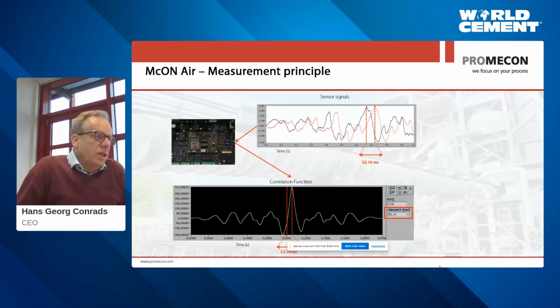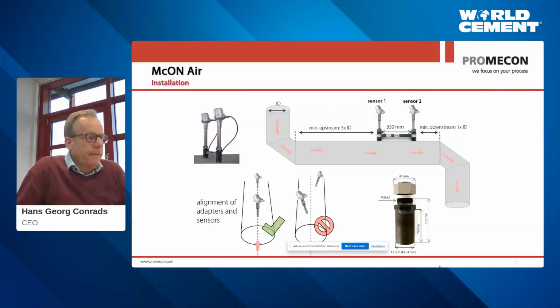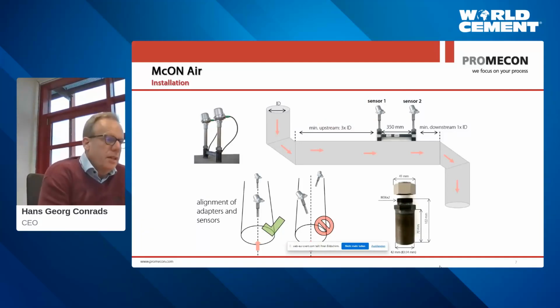What you can do then, of course, is you can compensate the measured velocity by the temperature of the gas and the barometric pressure. And of course, you should also take into consideration the cross-sectional area of the duct that this whole thing is happening in. So you have cross-sectional area times velocity gives you actual flow. And then compensation by barometric pressure and temperature gives you STP flow, standardized temperature and pressure flow. That's it. So what you do is you have this adapter and you weld it on to the duct, you put the sensors in, and then what you get is a time of flight, which you can then multiply with the cross-section area, compensate for temperature and pressure, and there you have your measurement.